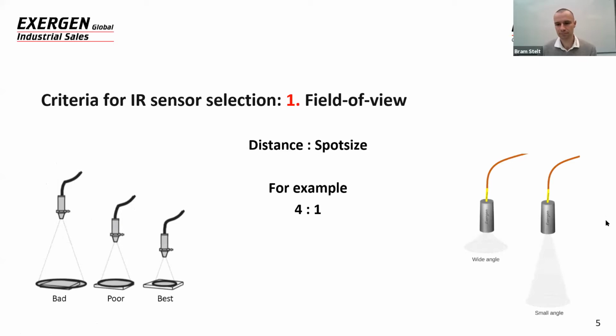Thank you. So the first criteria is called field of view, and field of view is defined as the ratio of the distance to spot size. For an example, a 4-to-1 field of view would mean if you're 4 inches away from the target, you would measure a 1-inch spot size. I apologize, I'm in the US, so I'm using English units.